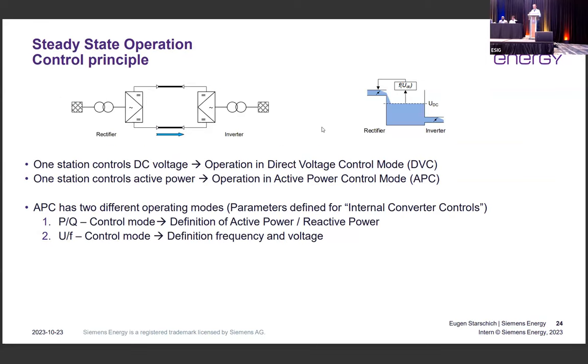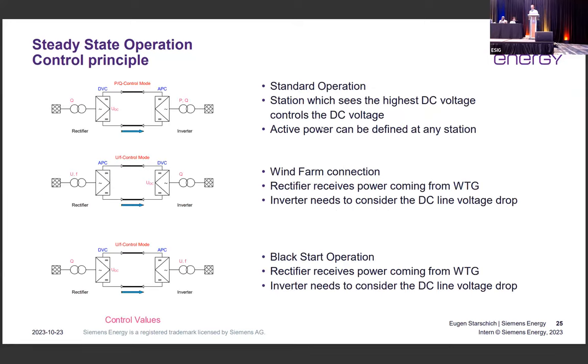A very quick look at the control principle. The main principle is that during steady state operation, we don't need any communication between rectifier and inverter. The coordination is done more or less completely through physical quantities, especially the DC voltage. And this is especially true for any AC fault ride-through. If the converter needs to operate in a faulty AC grid, this all has to happen without communication because it has to be very quick. So we don't rely on communication in this case. This is straightforward. This is the basic principle.